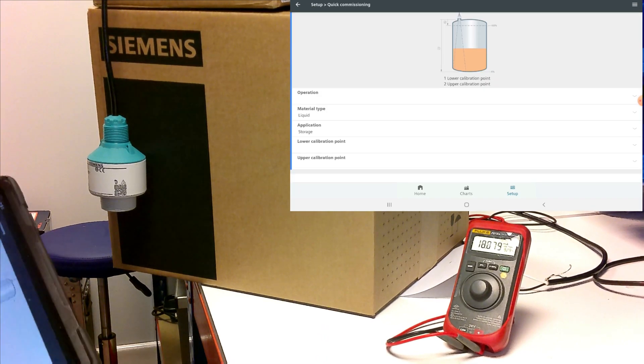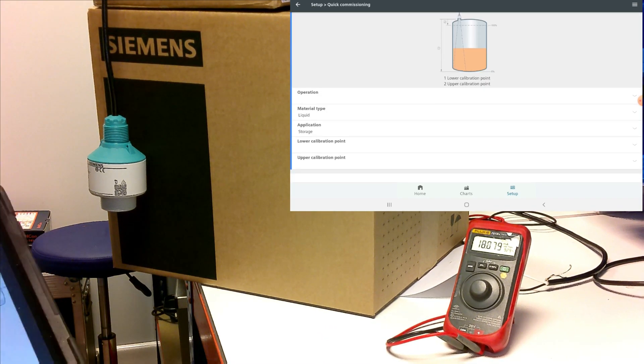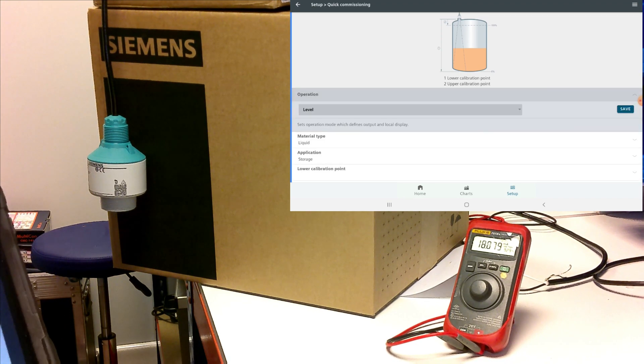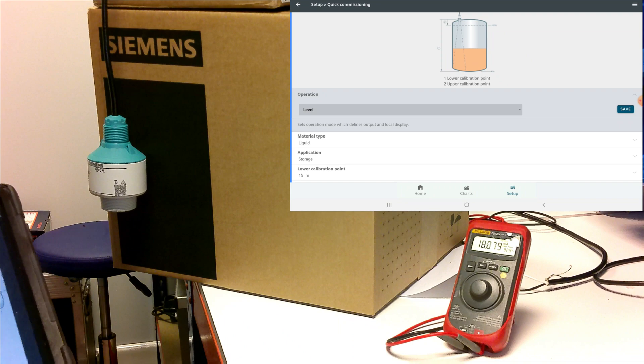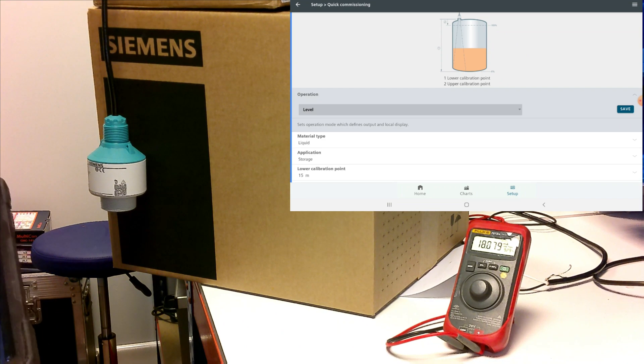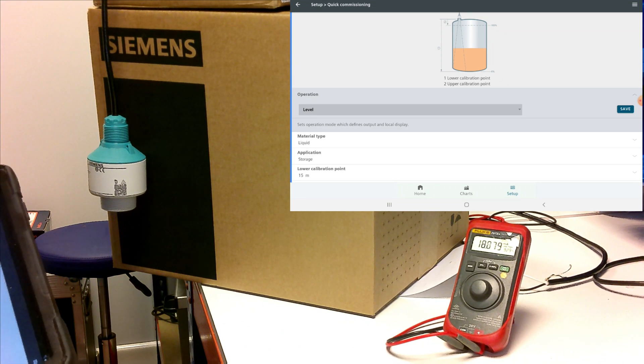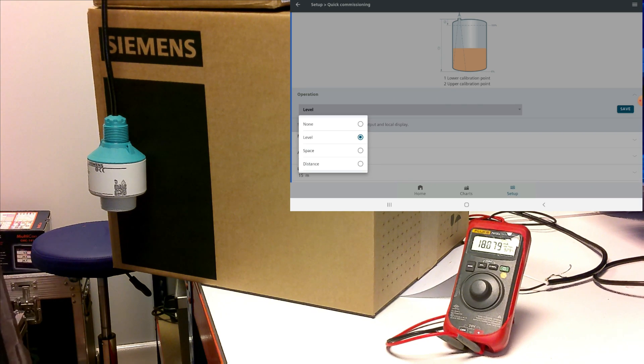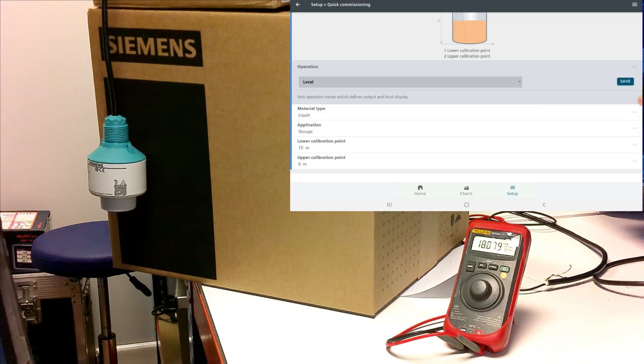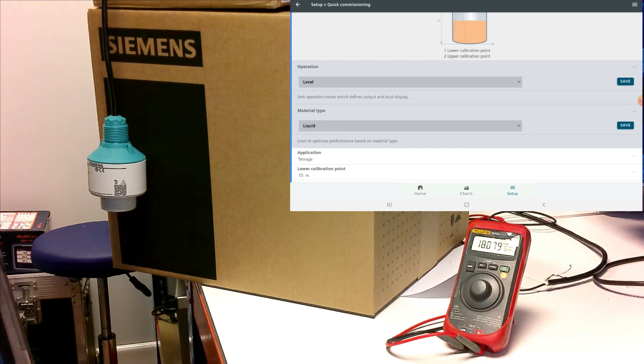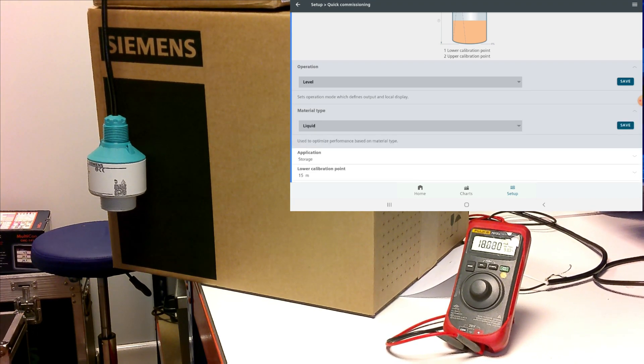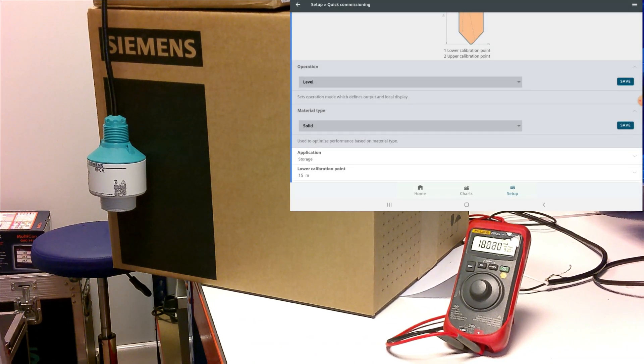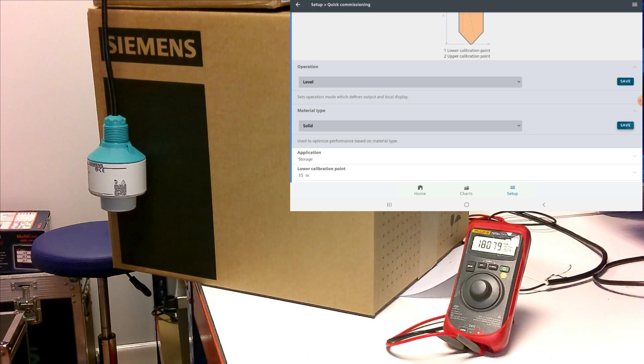Okay, what we're going to do here, there's a few settings that we'll set very quick and easy. The first one we want to set is the operation. Here we're going to do a level, but you could potentially change that to space or distance if that's what your application was. The next setting we want to have a look at is the material type. Here for our demo, we're going to change this from liquid to solid. Once you've changed a setting, if you want to load it to the device, tap save.